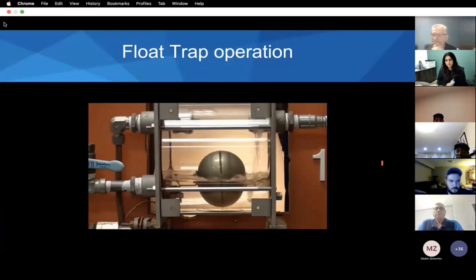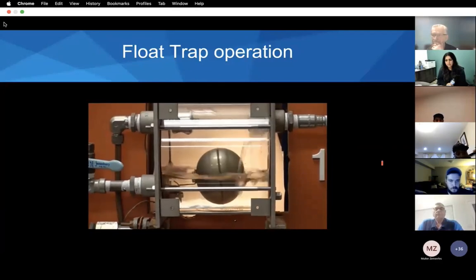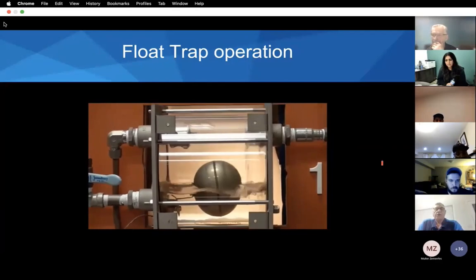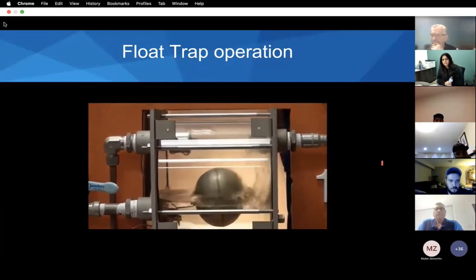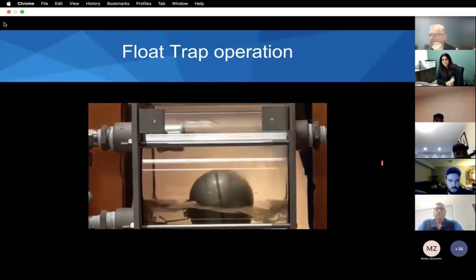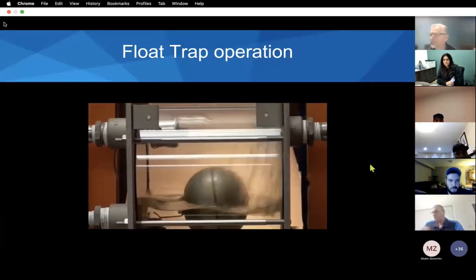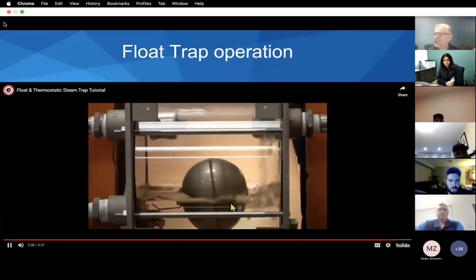The condensate level in the trap lowers and raises the float height, thus modulating the discharge flow. When steam reaches the trap, it collects above the condensate level and heats the thermostatic element, closing its valve. Hereafter, the thermostatic valve will open intermittently to vent mixtures of non-condensables and steam. Should the trap become waterlogged, cooled condensate would open this valve and drain to the discharge line.